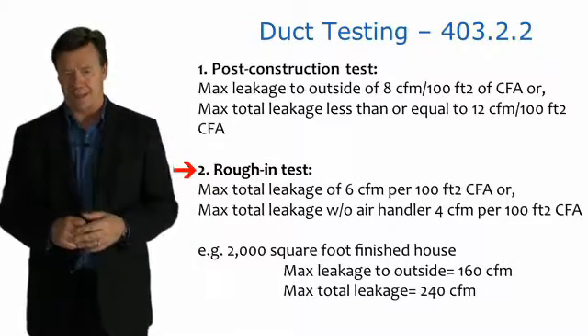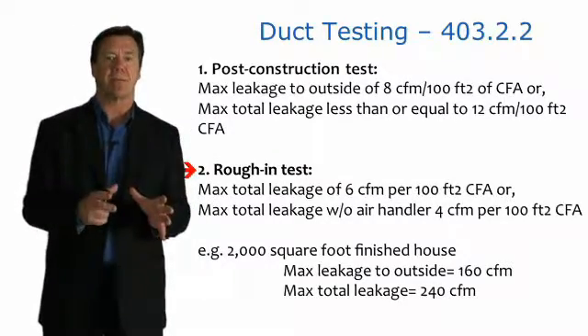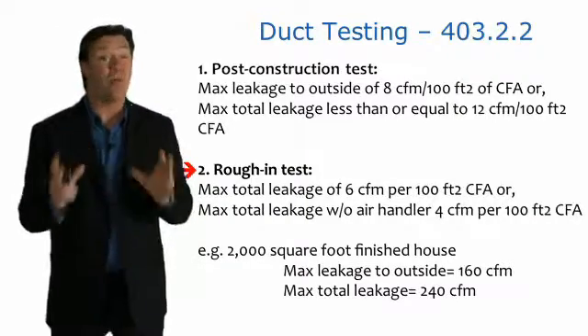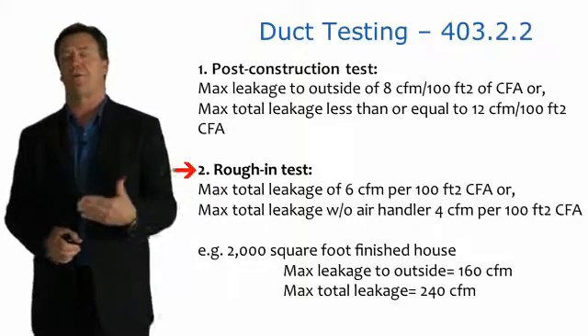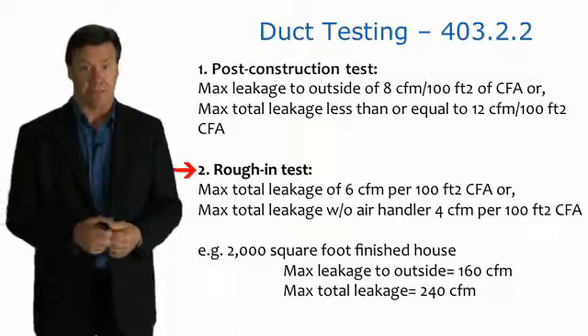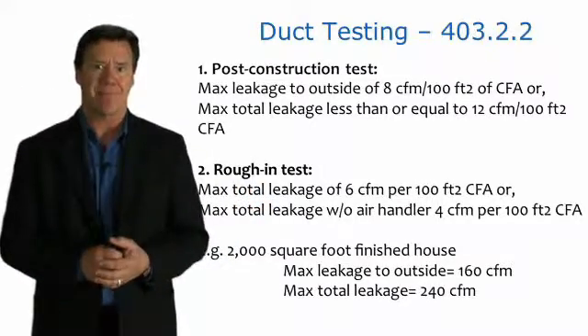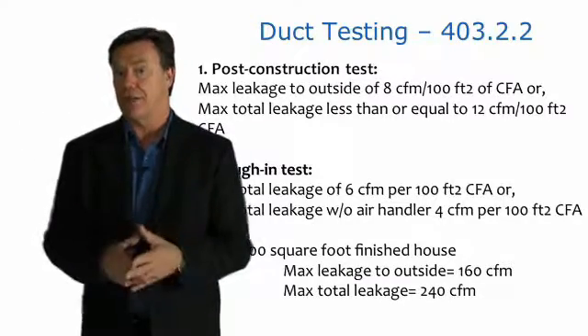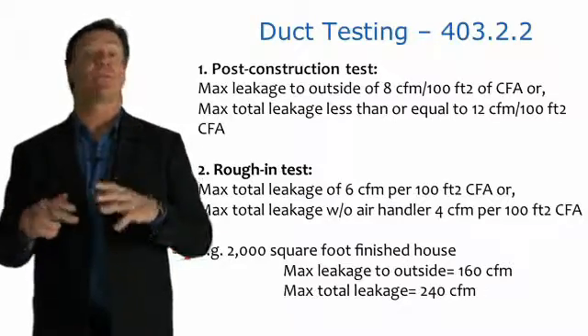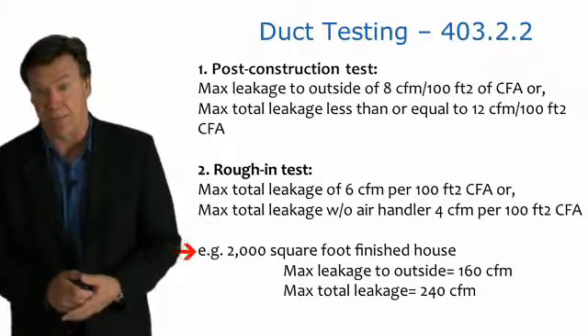The second approach is the rough-in test, which can be done before the air handler is installed or before the drywall is installed. For the rough-in test, the maximum leakage to the outside is no more than 6 CFM per 100 square feet of floor area, and the maximum total leakage without the air handler is only 4 cubic feet of air per minute per 100 square feet of floor area. This is actually a more stringent test because putting the rest of the system together adds more leakage. For a typical 2,000 square foot house, that means no more than 160 CFM leakage to the outside, and a maximum total leakage of 240 CFM — a fairly lenient number, but certainly better than the typical 300 to 400 CFM seen in many homes.